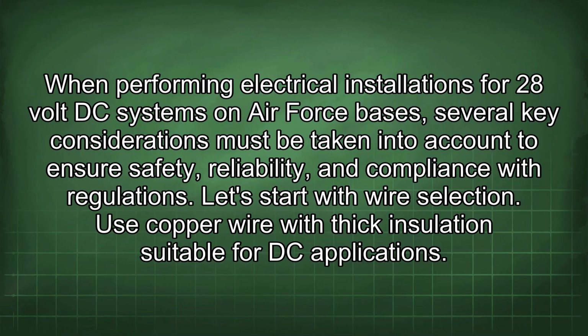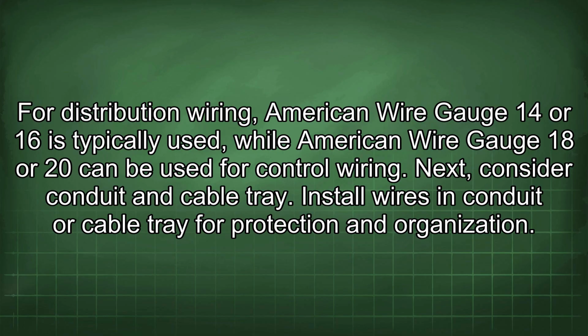When performing electrical installations for 28-volt DC systems on Air Force bases, several key considerations must be taken into account to ensure safety, reliability, and compliance with regulations. Let's start with wire selection. Use copper wire with thick insulation suitable for DC applications. For distribution wiring, American wire gauge 14 or 16 is typically used, while American wire gauge 18 or 20 can be used for control wiring.